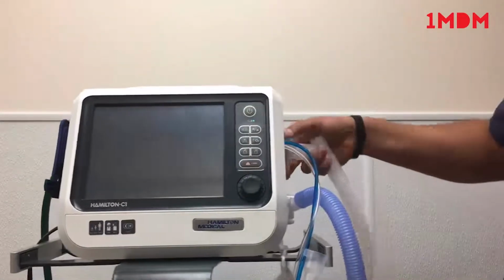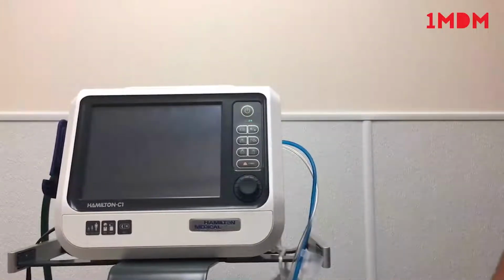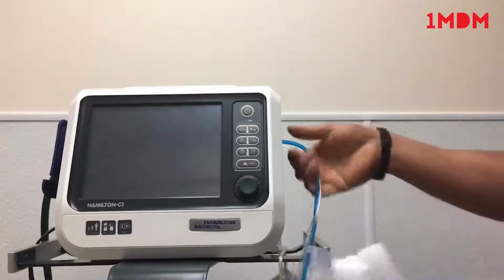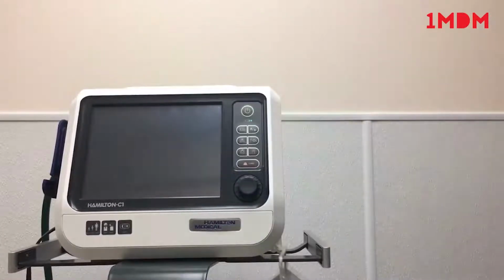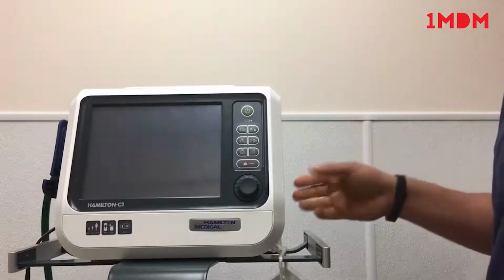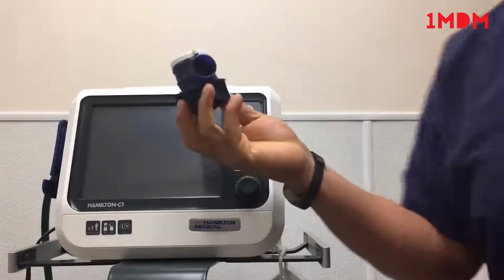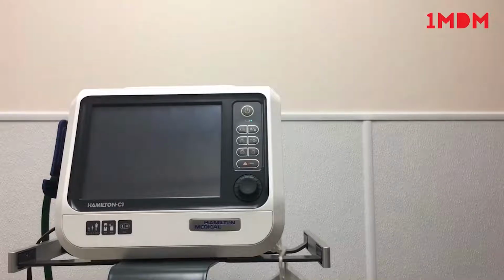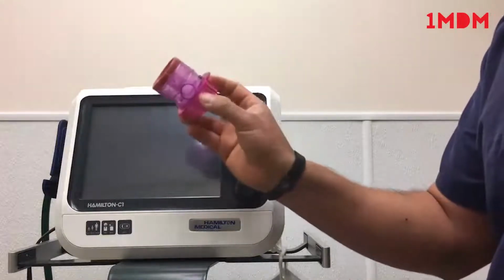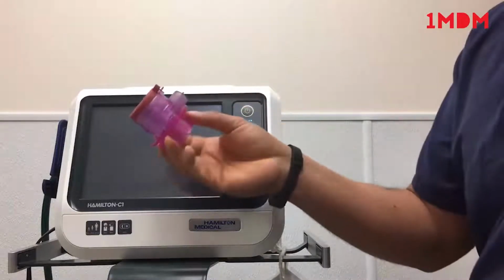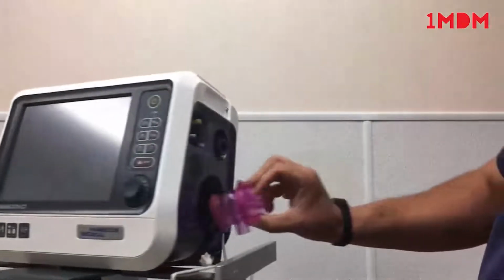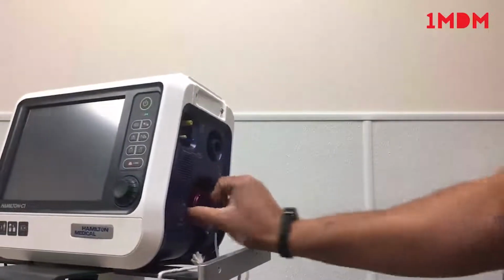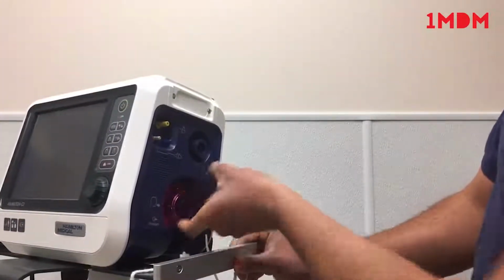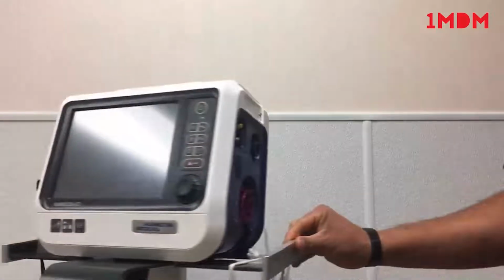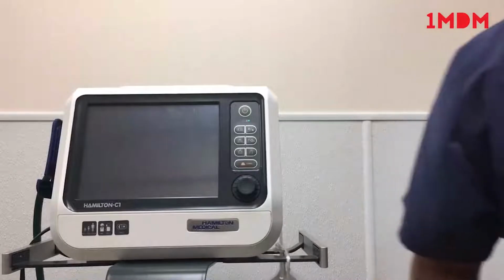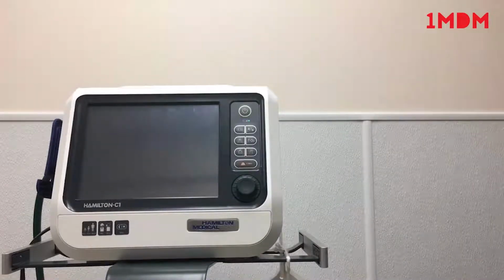First thing you're going to do is disassemble the adult respiratory circuit. Once you've disassembled the circuit, you also want to remove the exhalation valve. You now want to attach the neonatal exhalation valve. Now you want to make sure that it's securely fastened, that it doesn't move. So this seems to be on quite tight, which is a good thing. So now that that's done, we're going to move on to assembling the circuit.